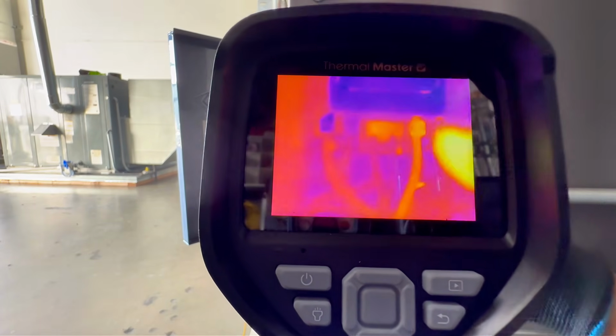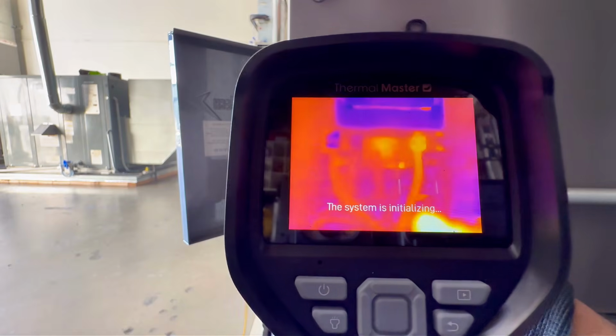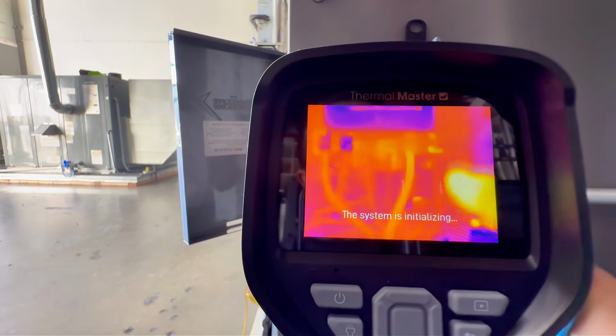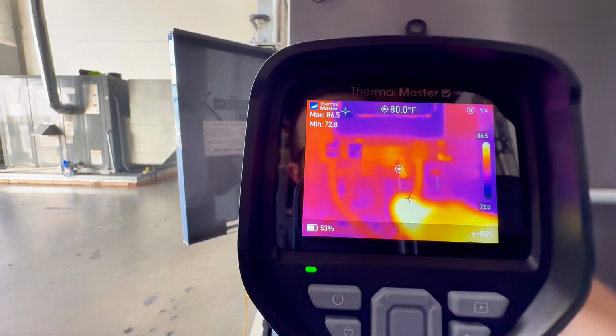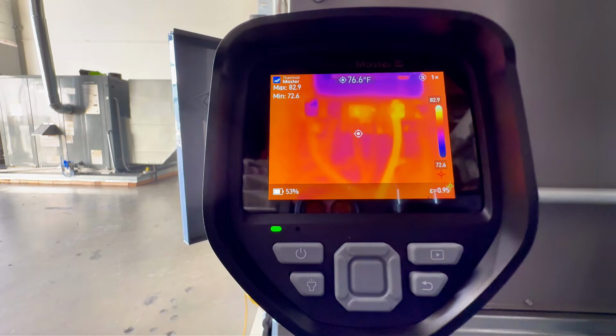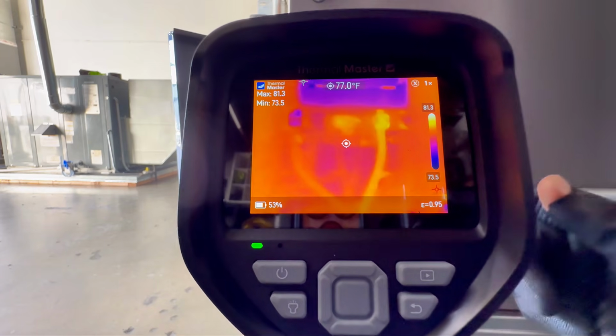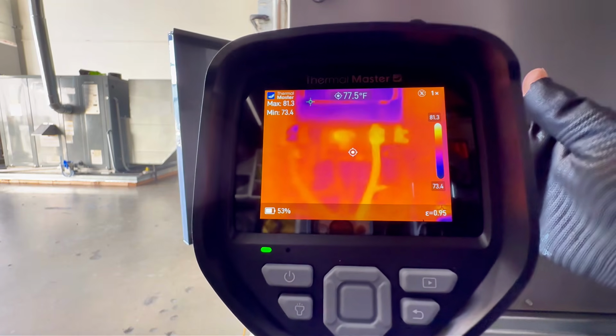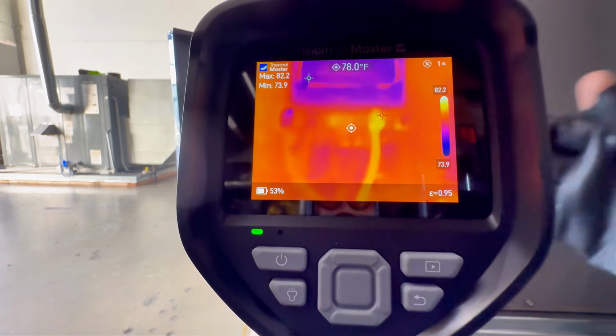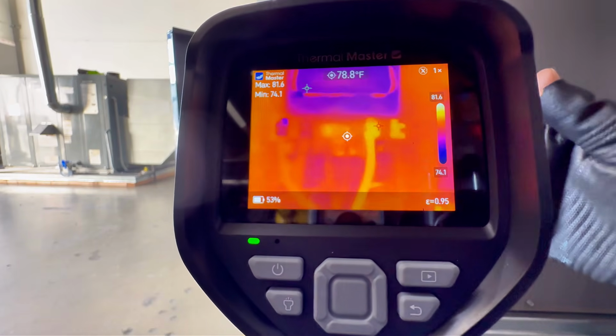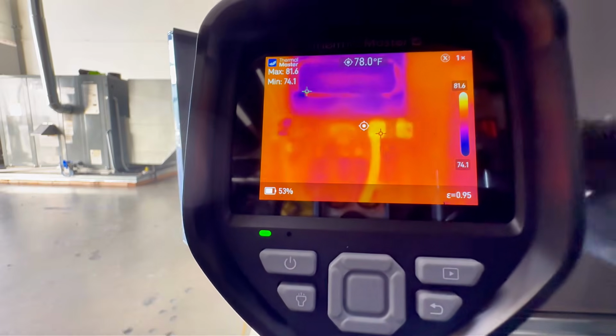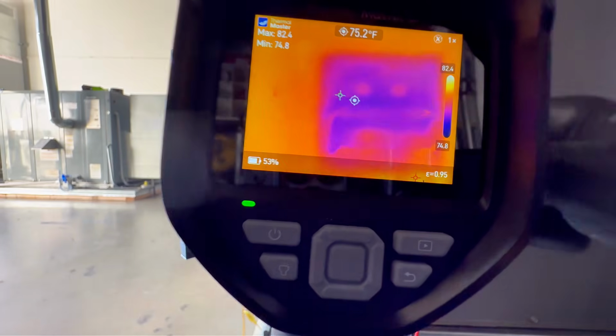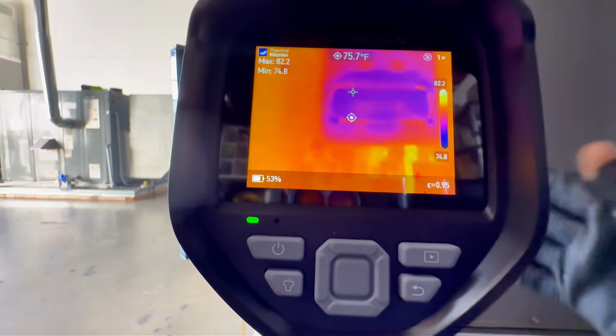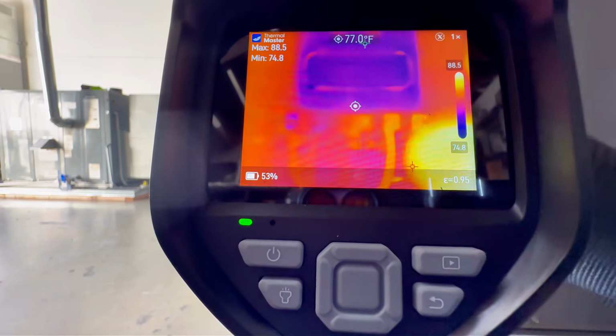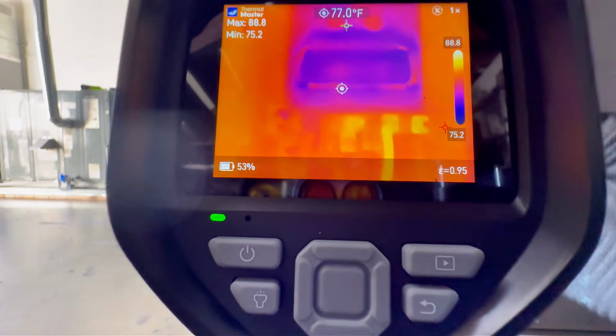So you see, so you got one wire there, another one right here. This is the one that was loose, and then this one here was the one that was okay. The one that's loose, look at the color. It's a lot brighter than the other ones because it's not tight enough. There's more resistance. Those electrons are making more impact because there's more resistance. It's not so much a conductor because it's loose. It's generating more heat, and that's what could cause your actual fuses to go bad. Your actual fuses can go bad because of that heat it's generating, because it's not tight, which is such an easy thing to do, right?